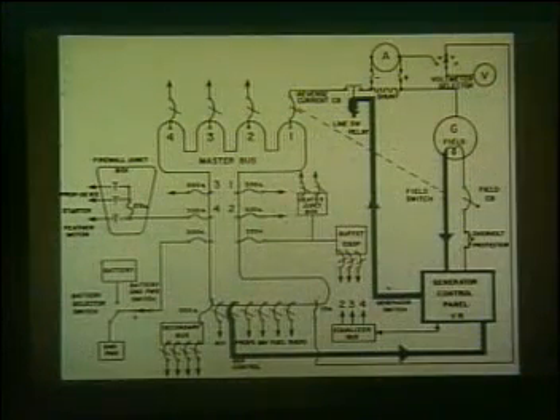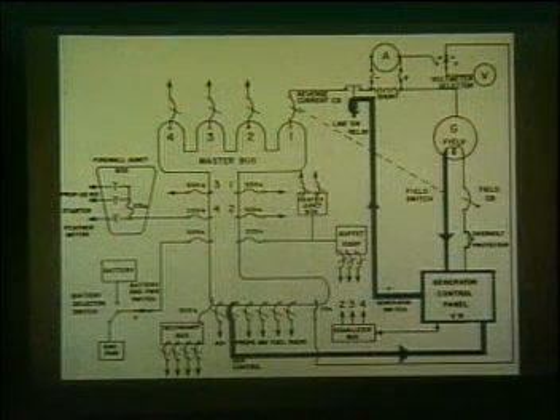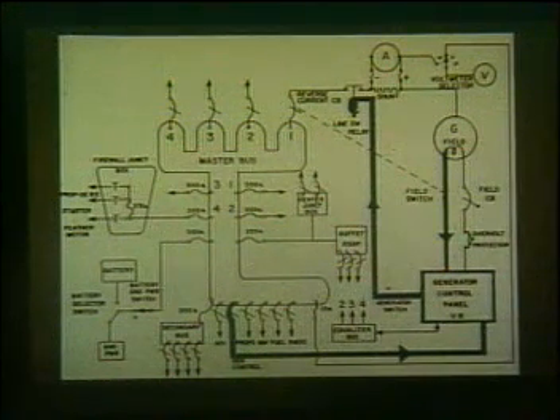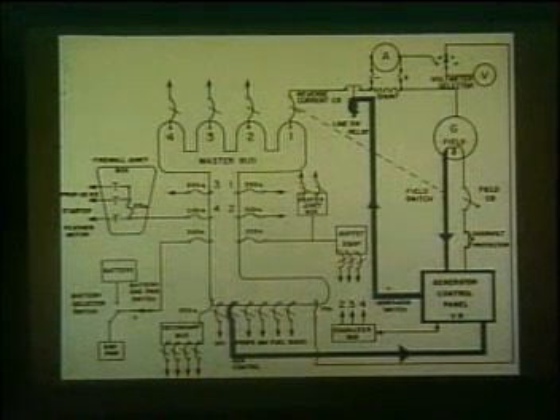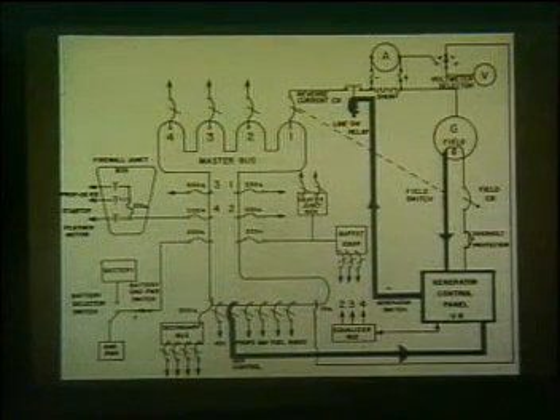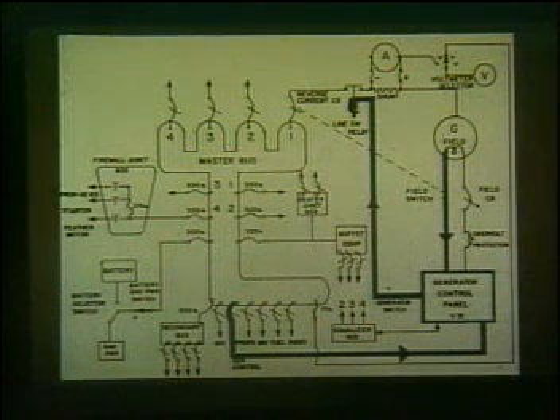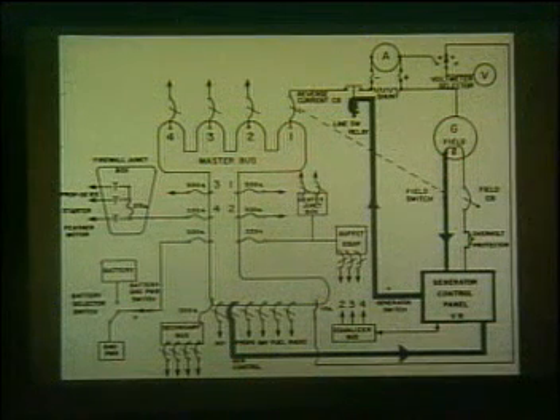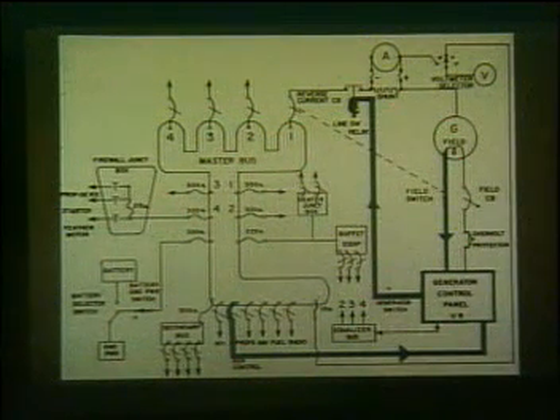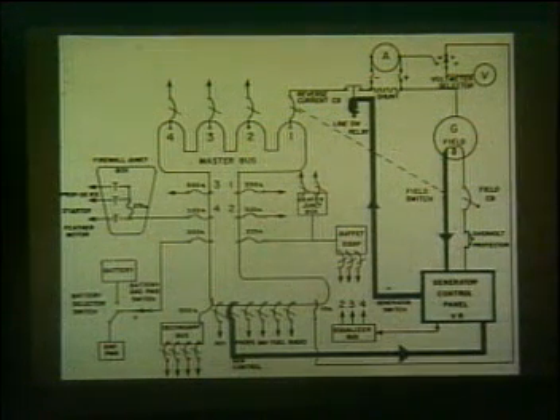The generator is automatically connected to the master bus when the generator output voltage gets slightly higher than bus voltage. This voltage differential is sensed by the generator control panel, lower right-hand box, which then allows the generator voltage to close the line switch relay, upper center. If this circuit breaker is tripped, there is no way for the generator control panel to receive a reference voltage from the bus. Consequently, the generator can never be connected to the bus.